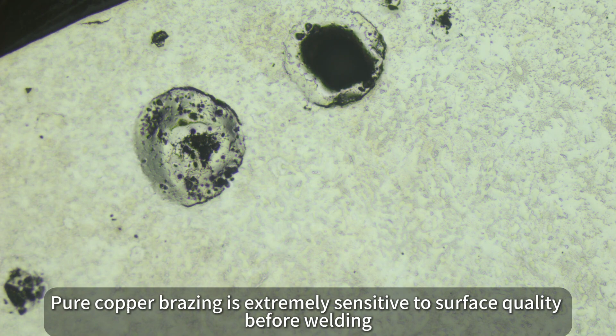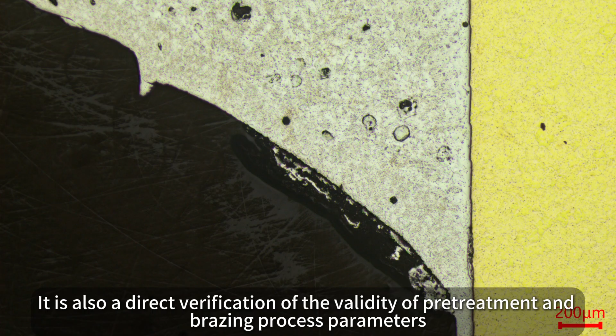Pure copper brazing is extremely sensitive to surface quality before welding. Before welding, it is necessary to strictly perform ultrasonic degreasing to remove oil stains. Then remove the surface oxide film by pickling. If there is an oxide layer on the surface, liquid solder metal will not wet the base metal, forming large areas of non-penetrating defects. During long-term hot and cold cycle service, such defects will directly evolve into leakage channels and cause the heatsink to fail. Therefore, metallographic analysis is not only the core means of welding quality evaluation, it is also a direct verification of the validity of pre-treatment and brazing process parameters.